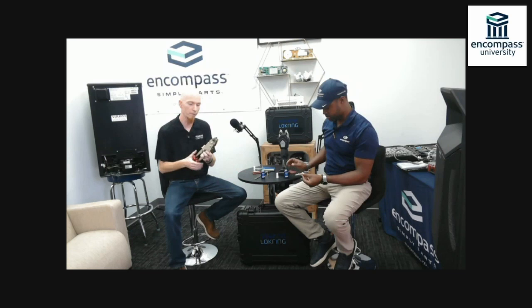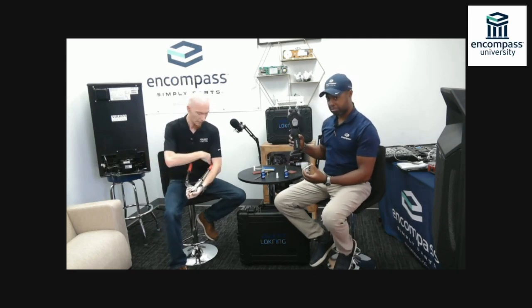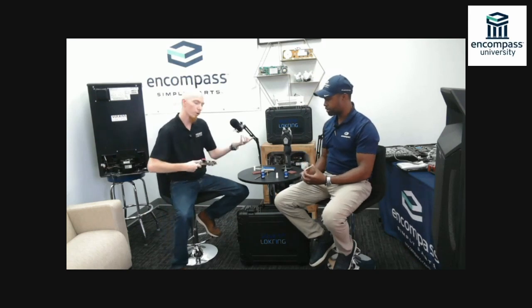I want to spin that connector a full 360 degrees to allow the Lokprep to be evenly distributed all the way around. From there I take my hand tool, bring my connector up inside of it, keep the tool running along my arm to stay nice and stable, and ratchet this all the way down.